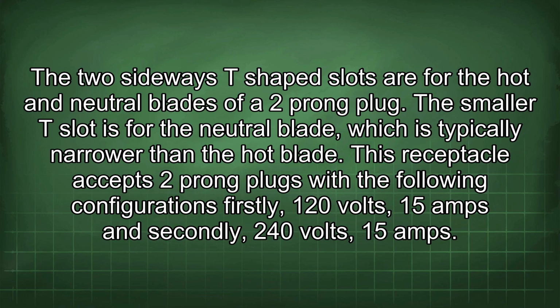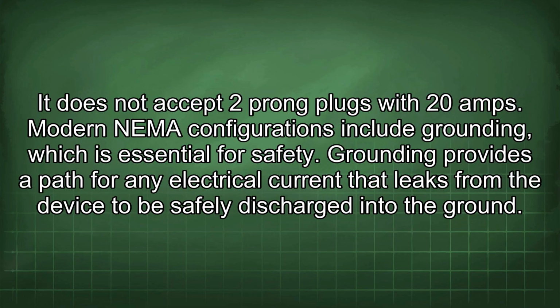This receptacle accepts two-prong plugs with the following configurations. Firstly, 120 volts, 15 amps, and secondly, 240 volts, 15 amps. It does not accept two-prong plugs with 20 amps. Modern NEMA configurations include grounding, which is essential for safety. Grounding provides a path for any electrical current that leaks from the device to be safely discharged into the ground.